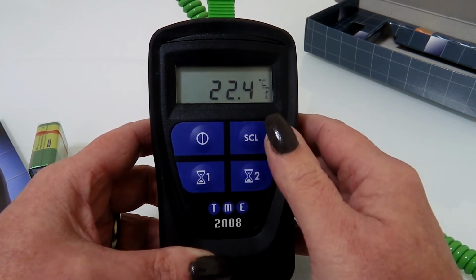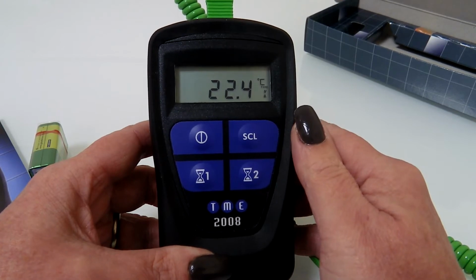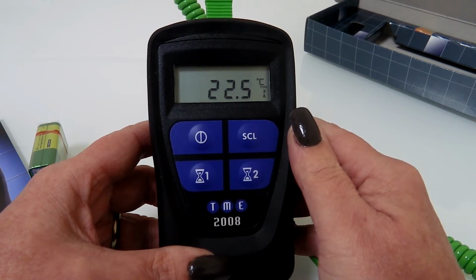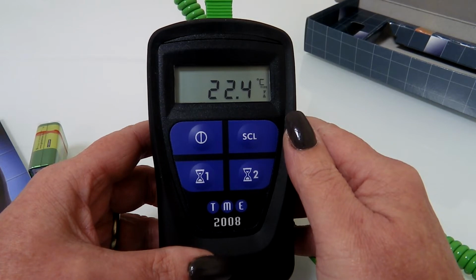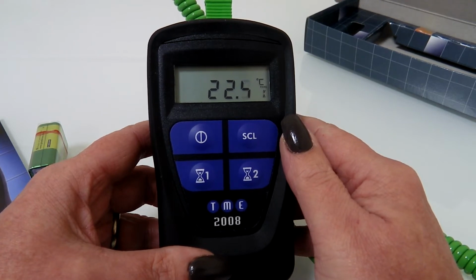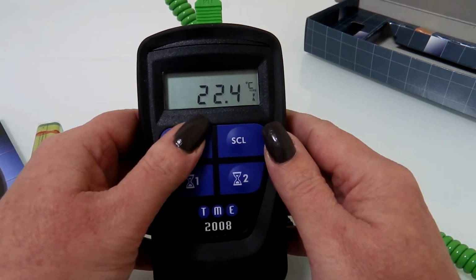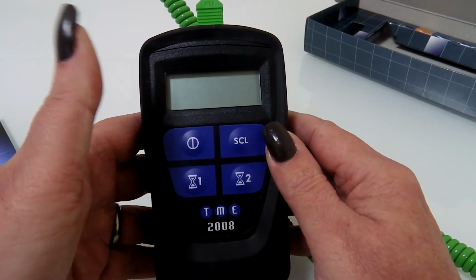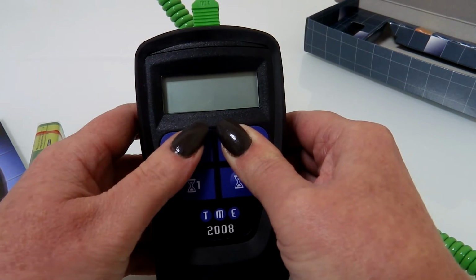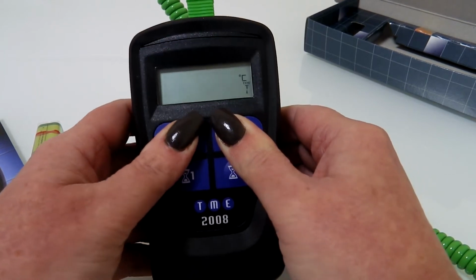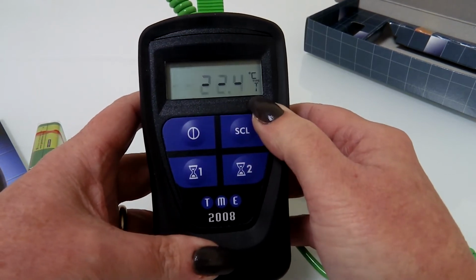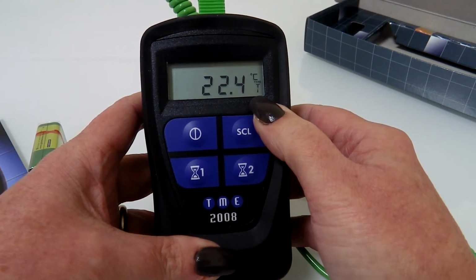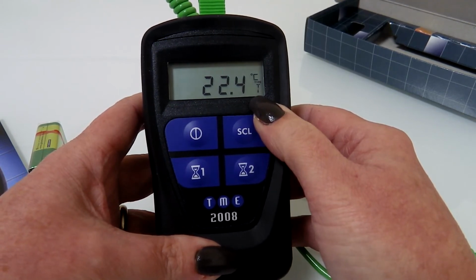Secondly, in conjunction with the on-off button, it enables us to change the thermocouple type. The MM2008 can be used with both K, that's green cabled probes, and T, brown cabled probes. Our display is currently showing K, but to change it for a T-type probe, switch the unit off, press and hold the SCL button, switch the unit on, then release the buttons. There, you see the display, the K is now a T.